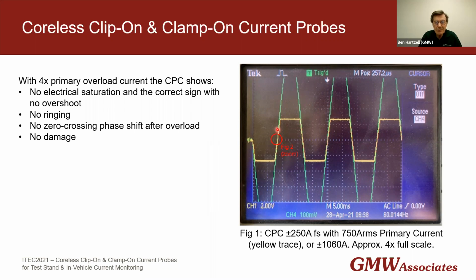And you can see that it very cleanly limits electrically. And there's no overshoot, there's no ripple. It's just a flat limit. And it also limits with the correct sign. So this is a positive going current, and the CPC limits positively. And then as soon as the current is within its range again, it follows the current.